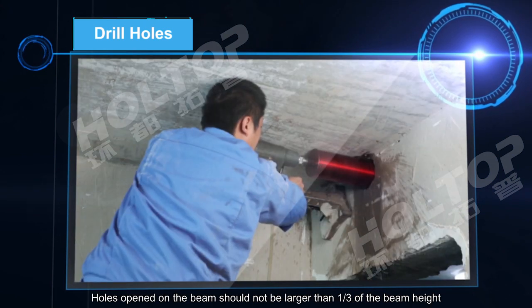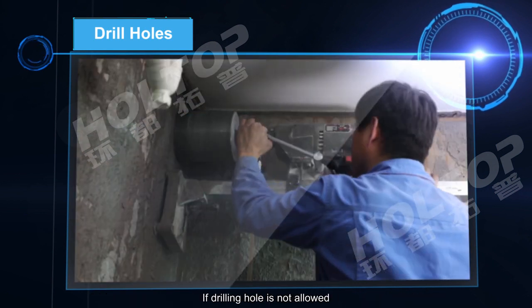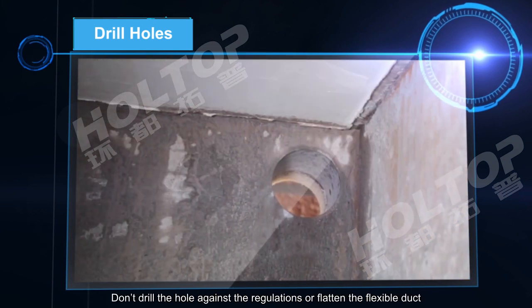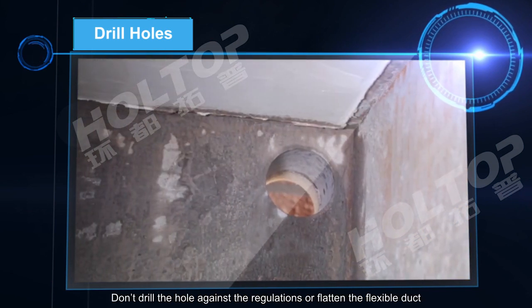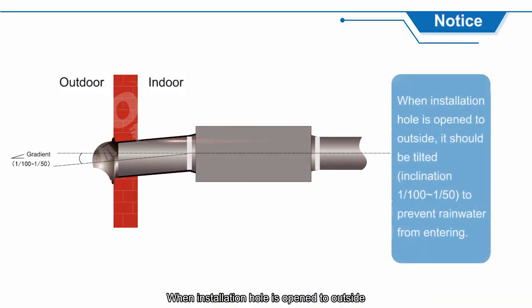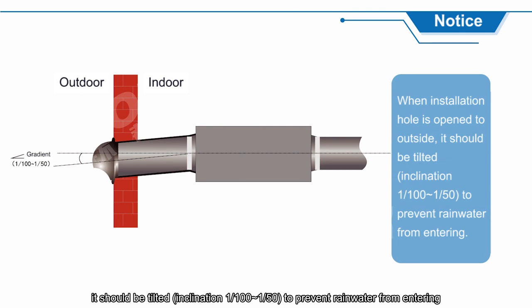The installation hole is drilled with a professional drill and must not be opened near the cross beam, pillar, or load-bearing structure, and must avoid lines embedded in the wall. Holes opened on a beam should not be larger than one third of the beam height; if drilling is not allowed, a lintel duct should be used. Do not drill against regulations or flatten the flexible duct. When the installation hole opens to outside, it should be tilted at an inclination of 1/100 to 1/50 to prevent rainwater from entering.